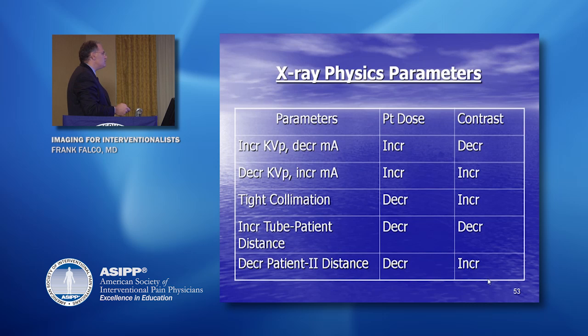Some physics parameters regarding kVp and current, your milliamps. You can see here that if you increase kVp and decrease mA, it increases patient exposure and decreases the contrast of what you're imaging. Doing the opposite, decreasing voltage and increasing current, you get better contrast but increased patient dosage. Tight collimation, great: decreased patient exposure, increased contrast, right? You get the best of both worlds with collimation. So collimation is really important.